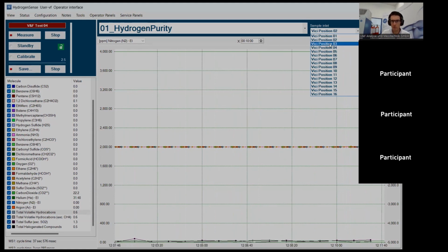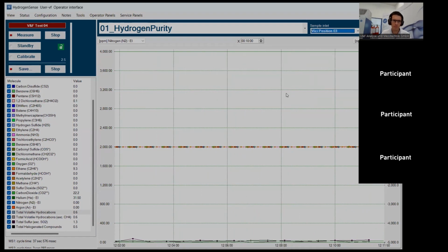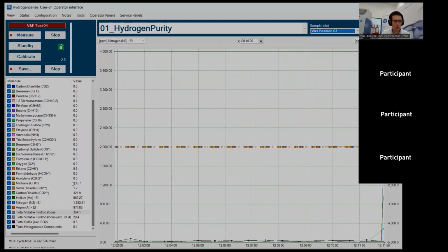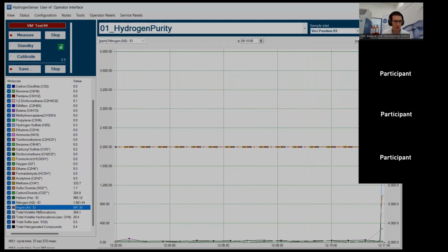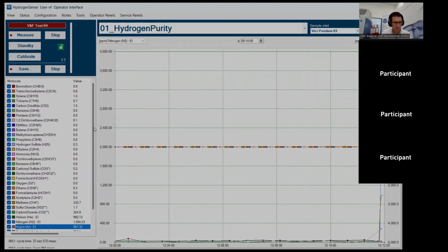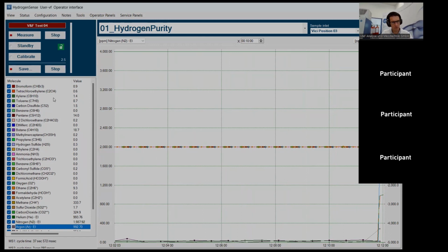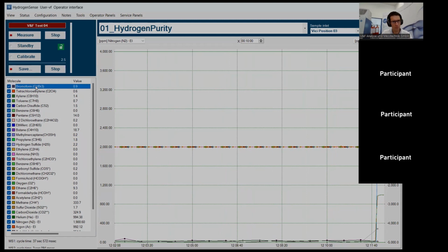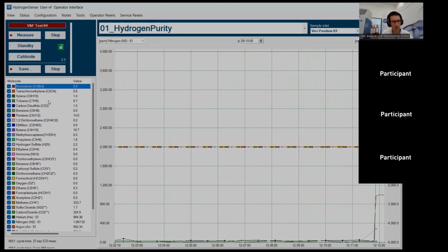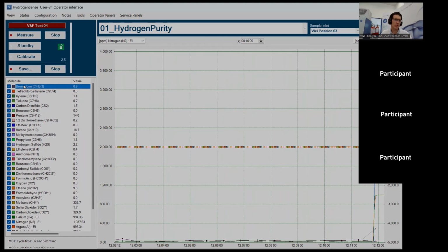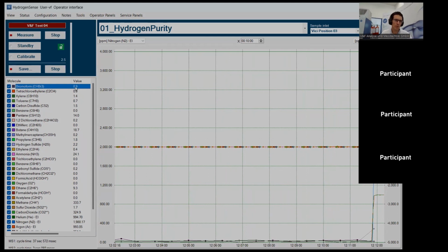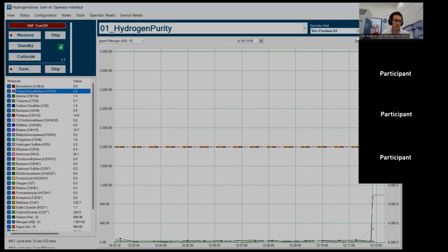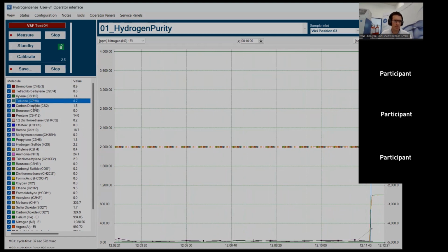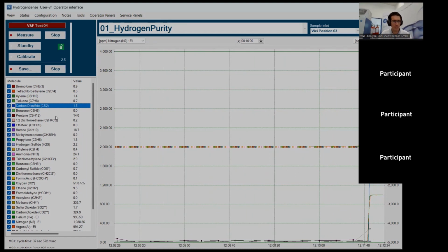So for example, if I'm switching here to position 03, this is a calibration gas bottle which contains helium, nitrogen, and argon. In order for you to get an impression of how these measurements work, you can imagine it like this. Each one of these molecules is pretty much a set of parameters for the instrument. So the measurement will proceed on one molecule, and then it will go to the next. Once this is finished, then it will go to the next, and to the next, and to the next. This is why we call that the measurement cycle.